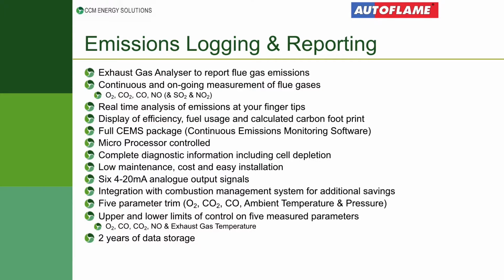What you'll see on this site here, which is one that I worked on in the US, is the control system is mounted here and our analyzer is mounted here, which is measuring those emissions. With the current exhaust gas analyzer, we're able to measure and report all of the flue gas emissions. So it's an in-situ stationary analyzer measuring oxygen, carbon dioxide, carbon monoxide, NOx and SOx, and it is unique to the boiler industry. Everyone talks about oxygen when they're measuring emissions from boilers. Oxygen trim. Oxygen trim is not safe. You need to be cross-referencing that with a second reading, whether that be carbon monoxide or carbon dioxide. This analyzer measures up to 6 parameters, and we can actually log the data that's coming off there. So it offers real-time analysis of the emissions at your fingertips.